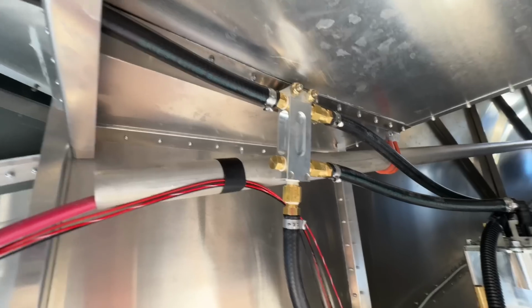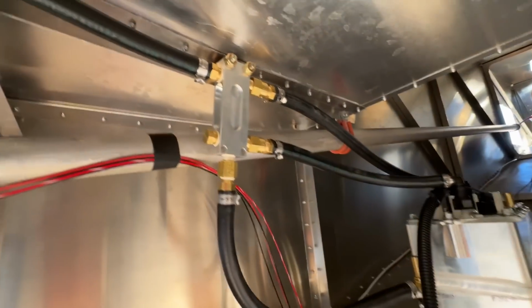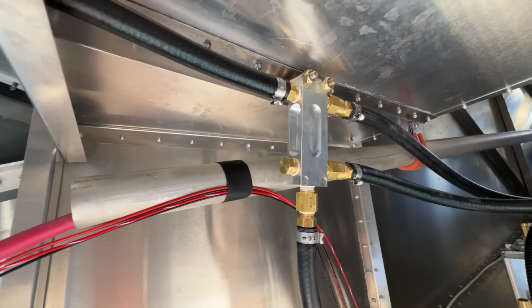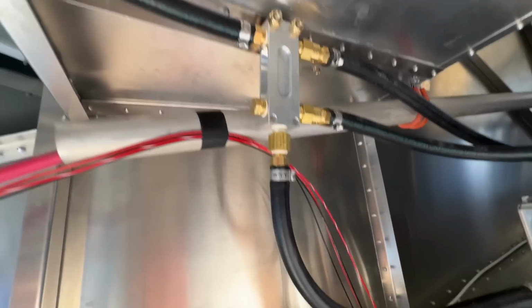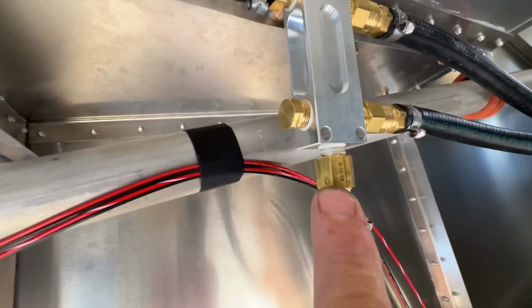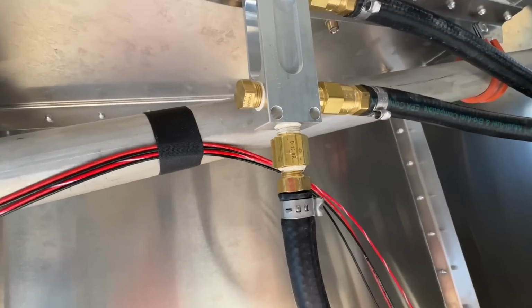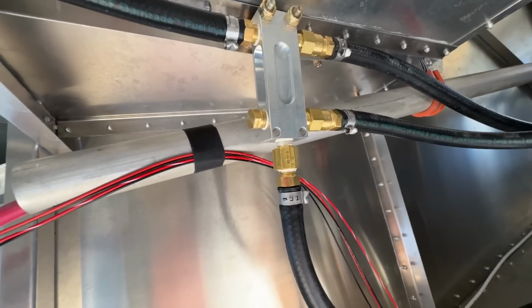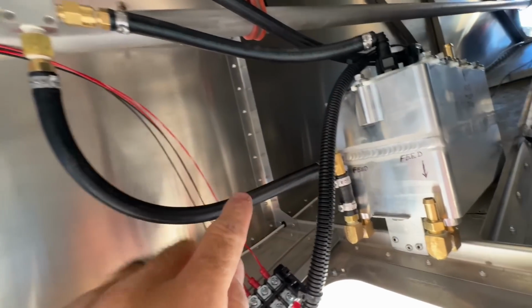Basically your pump pressure when the pumps are on should run 40 to 50 psi. Here's a little orifice, 10 thousandths, that's only there to bleed a little fuel back down to the low pressure side.